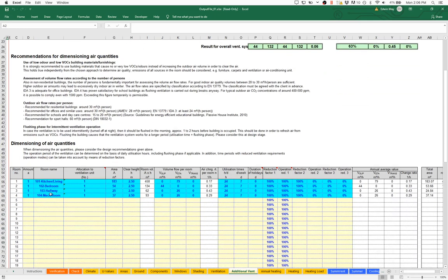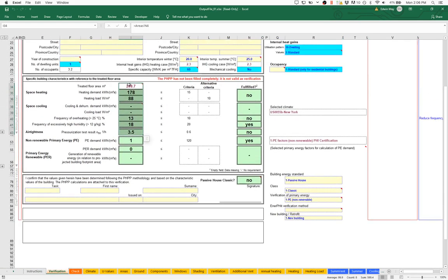If I scroll down a little bit, notice that I have here a listing of all of the various rooms with their areas, their ceiling heights, and their fresh air supply — fresh air ventilation supply — as well as schedule information about how the fresh air system is running. A lot of this is using defaults: right now it's running at 100% fan speed, 100% of the time, 24 hours a day, seven days a week — not very realistic. But all that information is flowing through correctly, and if we go back to our verification worksheet, we're getting our TFA accurately assessed based on those rooms and their net interior floor area.